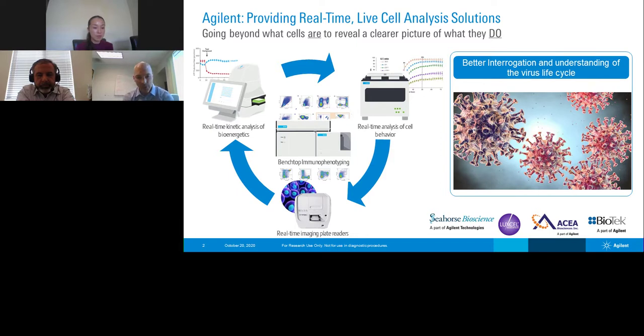For Xiaoyu, another question was, can the CardioECR plates be reused? Yeah, we heard about that a lot. No, especially for the CardioECR plate, because the electrodes are very, very sensitive. We already know that the cleaning process is going to damage the electrodes. There are a couple of reports from our users saying that if you reuse the plate, you will see a large standard deviation during your assay. So we don't recommend you reuse the plate.